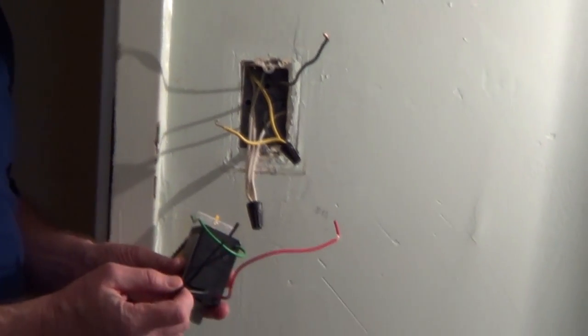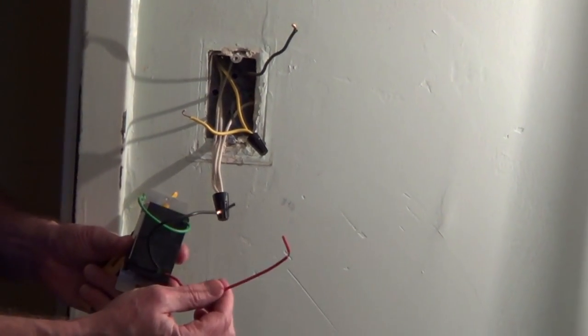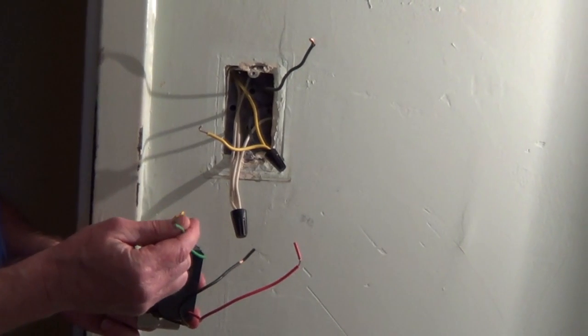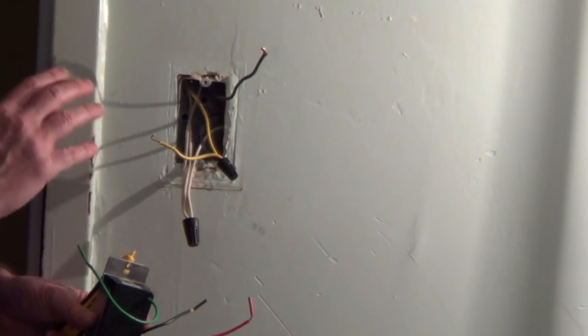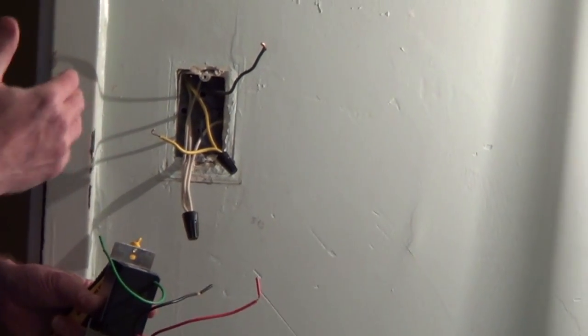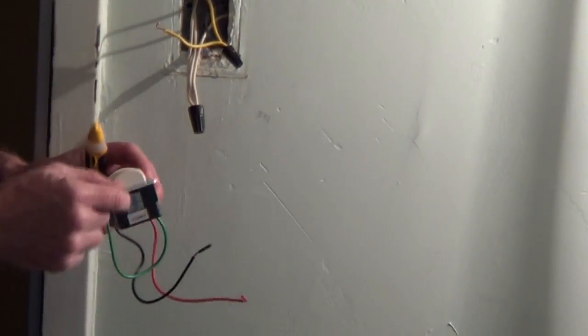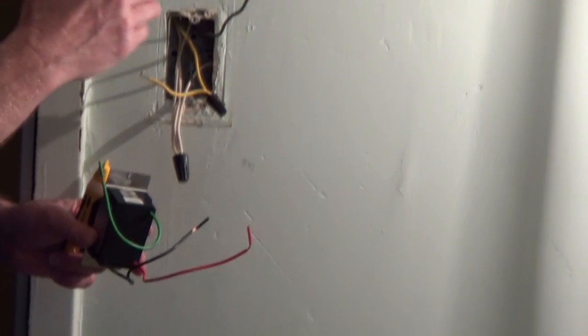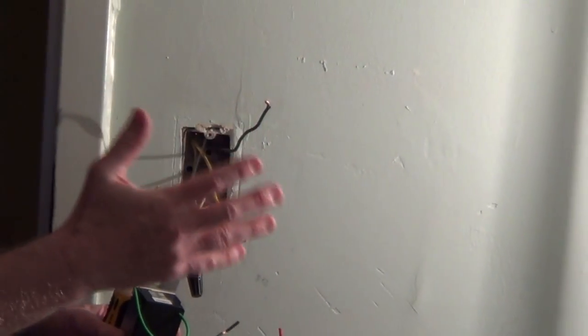So black wire from the service panel, the red wire to the load and a green wire if you had a ground in here. Now we're in the Chicago area and we have all metal conduit and so when we screw this in with metal screws it's going to be grounded to the box and then the metal pipe all the way back to the service panel.